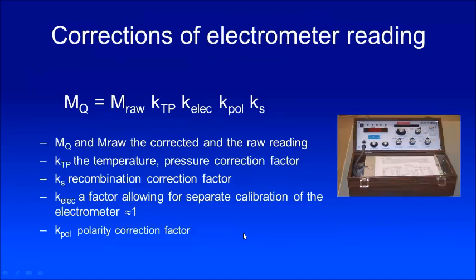The corrected electrometer reading M_Q for user beam quality Q is the raw meter reading in nanocoulombs corrected for temperature-pressure, polarity correction, recombination correction, and if applicable, the electrometer calibration factor.